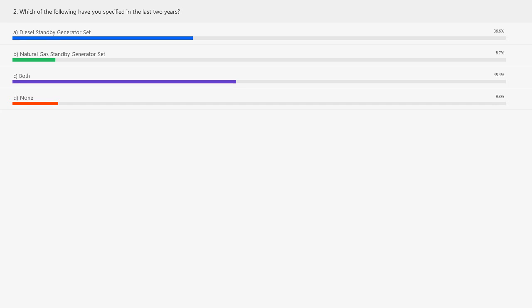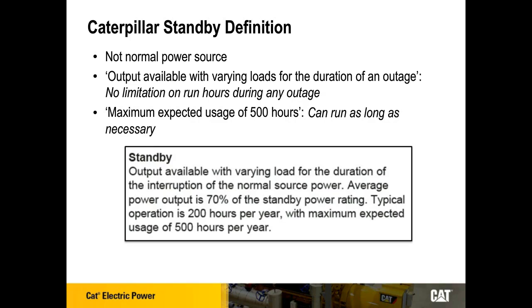With that, back to you Bailey. As we dive in, let's define what a standby application means at Caterpillar. It means the generator is not the normal power source, and we don't expect it to run more than 500 hours a year. For most standby applications that would be unusual, but the generator set is designed to run longer if an outage requires it. We also expect that when loads are on the generator, they vary and average about 70%.